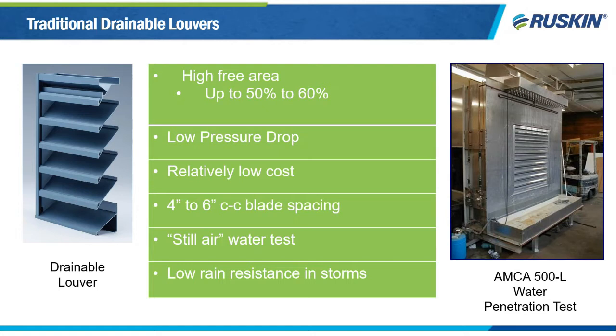They typically provide a high amount of free area, 50 to 60% in sizes 48 by 48 and larger, and the pressure drop through them is usually low, around 0.05 inches water gauge or less at 500 feet per minute free area velocity, which is a common design level for this type of louver. These louvers have blades that are usually widely spaced apart, typically 4 to 6 inches on center, and they're tested in what we call the AMCA still air test, which subjects them to ventilation airflow and water, but no wind. Drain gutters in the blades and frames allow these louvers to perform well in that test, even with their large blade spacing.